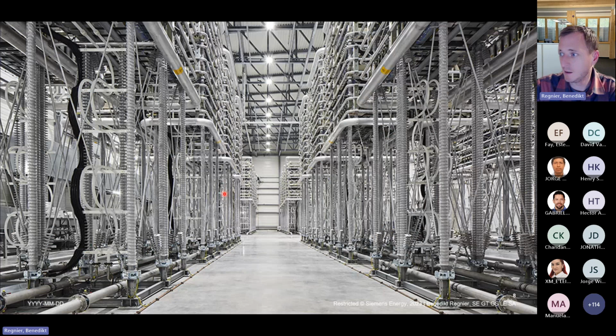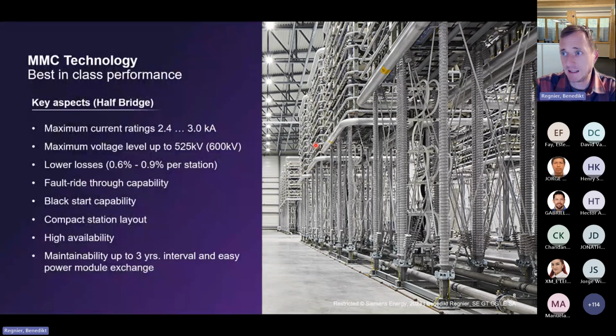Putting everything together, we end up here with converter towers like this. The key aspects again of our MMC converter: the current rating, as said, we can go up to 3 kiloamps. And the typical voltage level at the moment is up to plus and minus 525 kV, so the real DC operating voltage is 1050 kilovolt. We can also go to 600 kV, always depending a bit on the factors of what we need to serve here. Our converters have very low losses, which is very important because no customer gets paid for the losses. So we strive to optimize that.